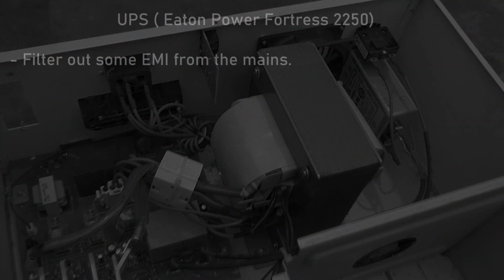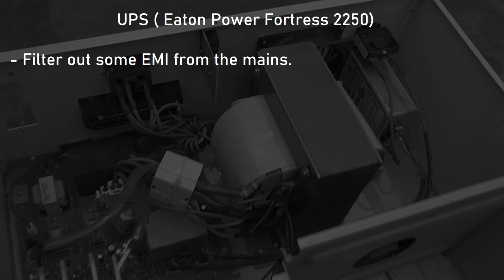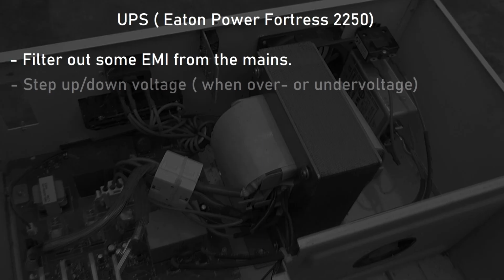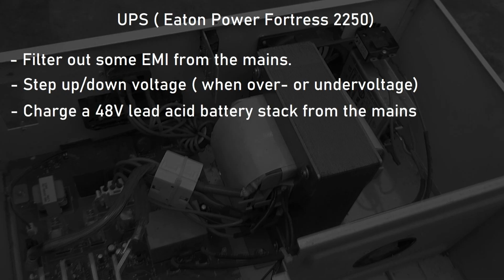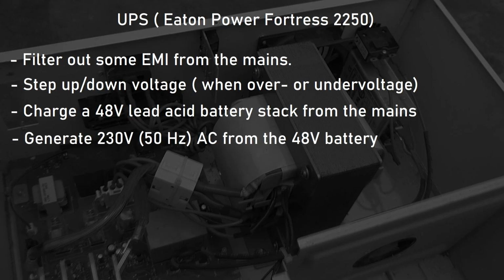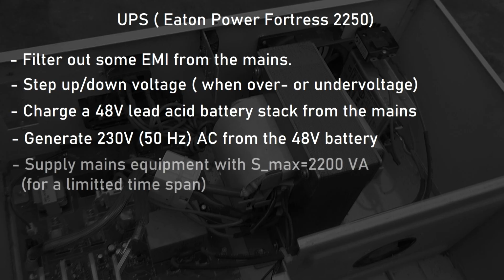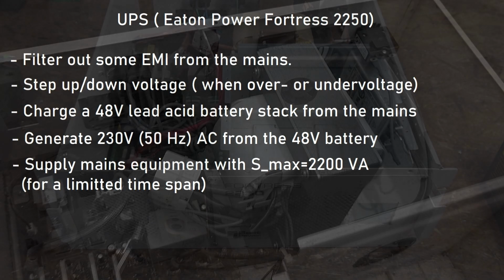This particular UPS can do the following things: filter out some electromagnetic interference from the mains, step up or step down the supply voltage in case of overvoltage or undervoltage conditions, charge a 48 volt lead-acid battery stack from the mains electricity, generate a sinusoidal alternating voltage of 230 volts from the 48 volt battery, and supply mains equipment with a maximum apparent power of 2200 VA for a limited time span.